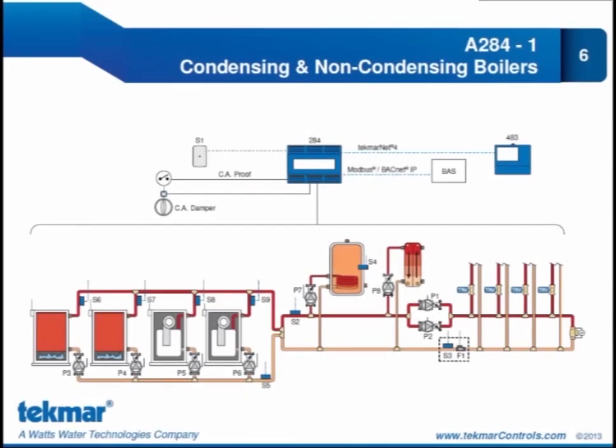This first application is showing a mixed heating plant. We have 2 single-stage non-condensing boilers, and we have 2 modulating condensing boilers. And all 4 boilers are being used to provide heat for indirect domestic hot water, a set point load, and for space heating. You can see we have 4 space heating zones equipped with TRVs. Also note we are doing primary pump sequencing for a standby operation of the primary pump. We can do this along with indirect domestic hot water, whereas in the 274 and 275 it was one or the other. With the 284 we can do both, so a real advantage to the 284.